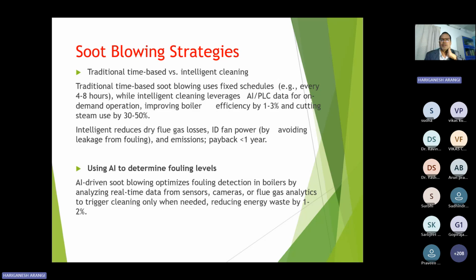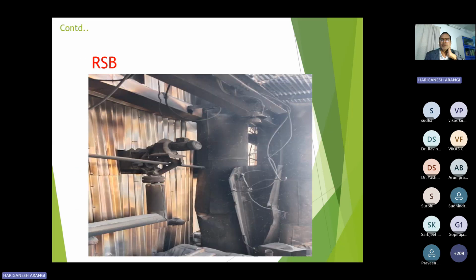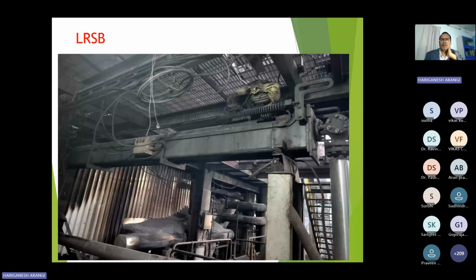When you are doing a soot blowing, there will be a consumption of steam and there will be a motor also, so power also will be consumed. These two things can be saved if there is properly AI-driven monitoring. This is an example of a rotary soot blower. And this is the long retractable soot blower. There will be a lance. When it operates, it goes inside the boiler and cleans.